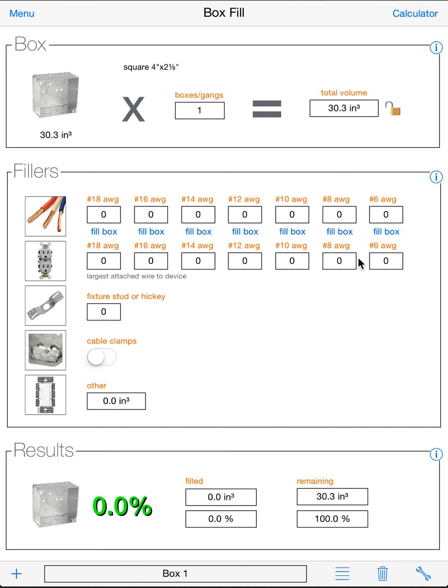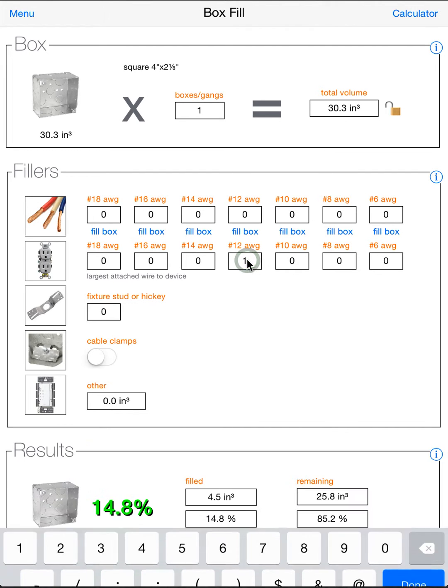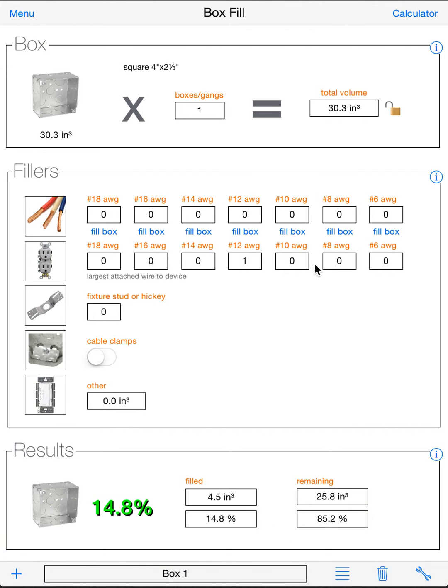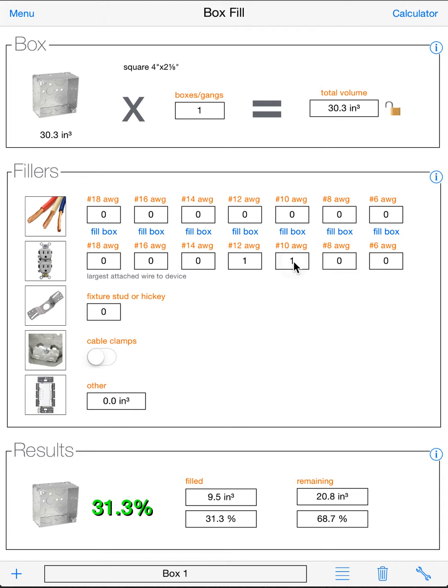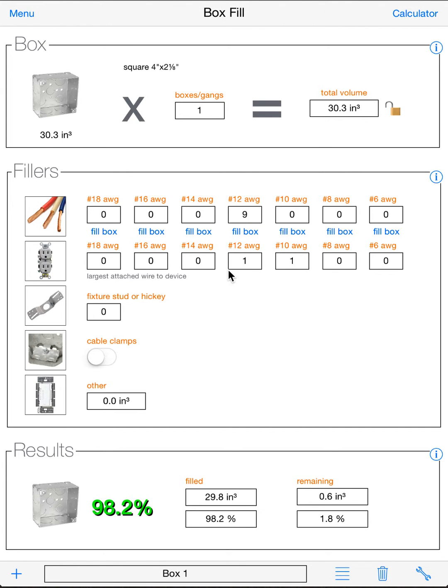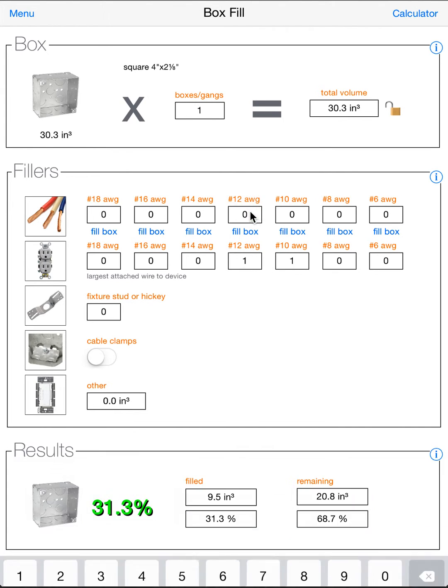Next is your devices. The devices are based on the largest wire wired to the device. So if you have a receptacle with number 12 wire on it, you will add a one here. If you have a larger receptacle, say a 30 amp receptacle or something for a dryer or a heater or whatever, you'll add that here. Now you'll see if I go fill box with number 12s, it'll only go to nine because we already have fillers in there.